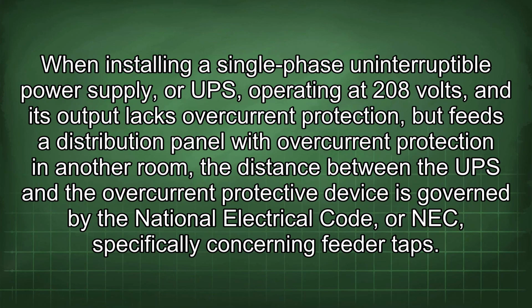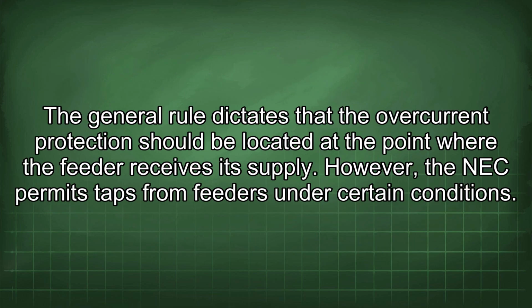When installing a single-phase uninterruptible power supply, or UPS, operating at 208 volts, and its output lacks overcurrent protection but feeds a distribution panel with overcurrent protection in another room, the distance between the UPS and the overcurrent protective device is governed by the National Electrical Code, or NEC, specifically concerning feeder taps. The general rule dictates that the overcurrent protection should be located at the point where the feeder receives its supply. However, the NEC permits taps from feeders under certain conditions.